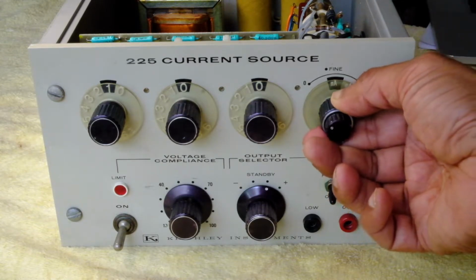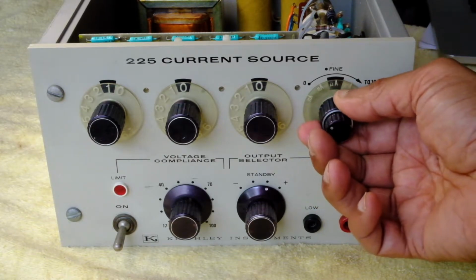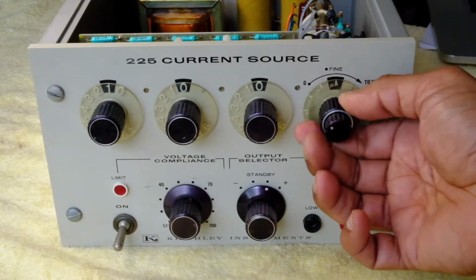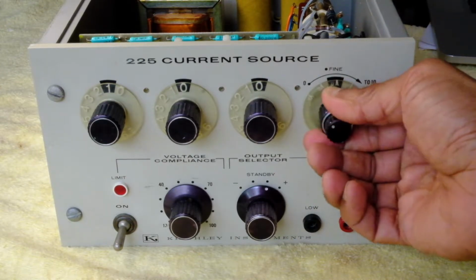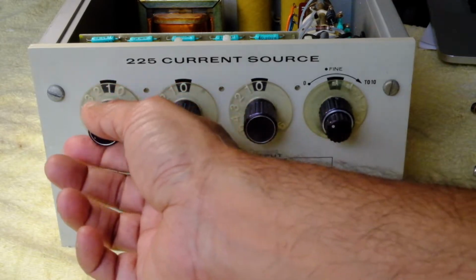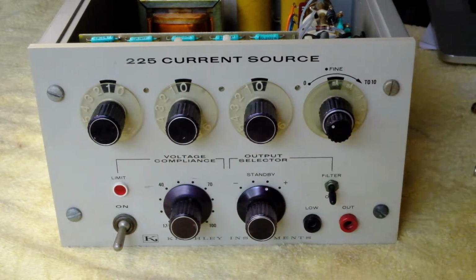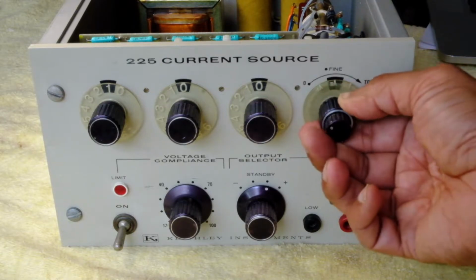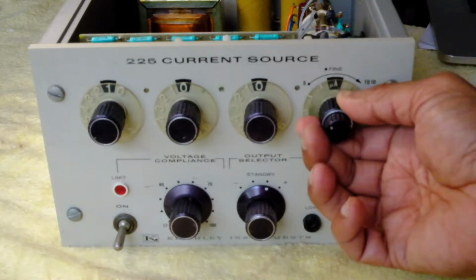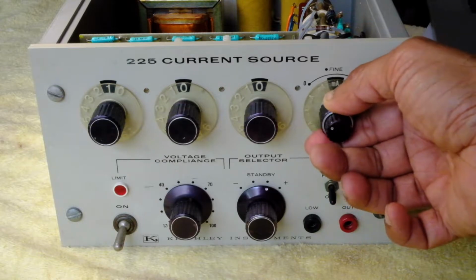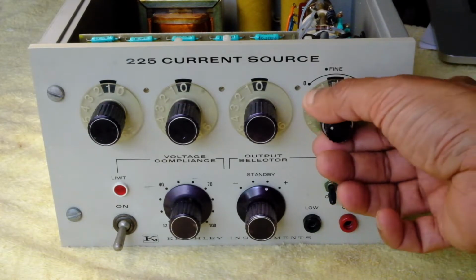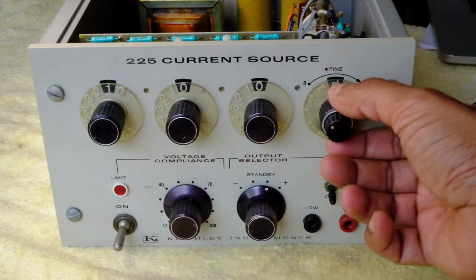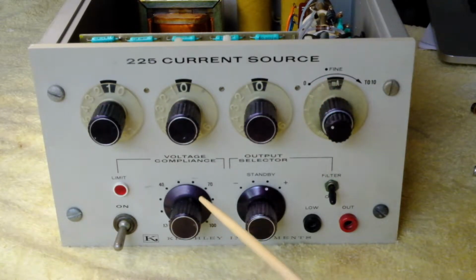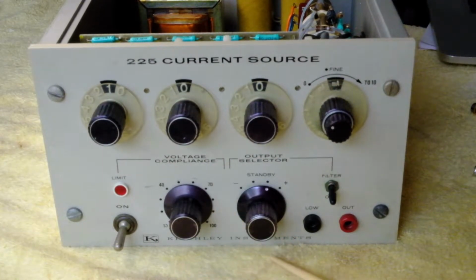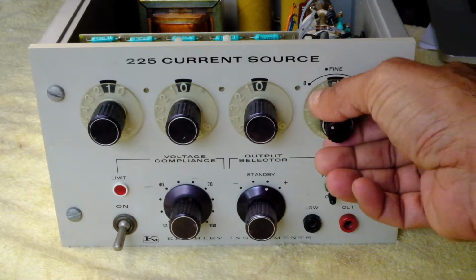Then the decade resistance sets the value of the current in various decades, starting from a minimum of 100 nanoamps, and the decimal point is indicated by these lights when it's on, all the way up to, there are 7 ranges here, up to 100 milliamps in this particular case, extreme right. So that basically describes the unit. It's fairly simple to operate, as you can see.